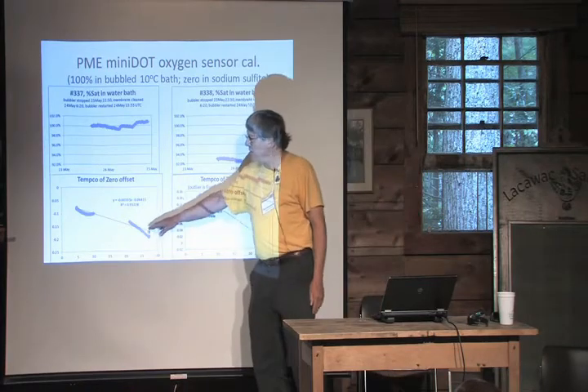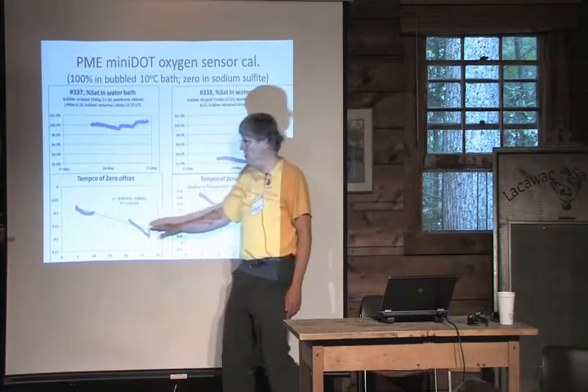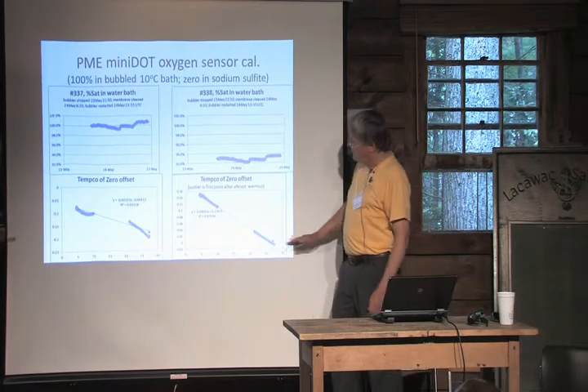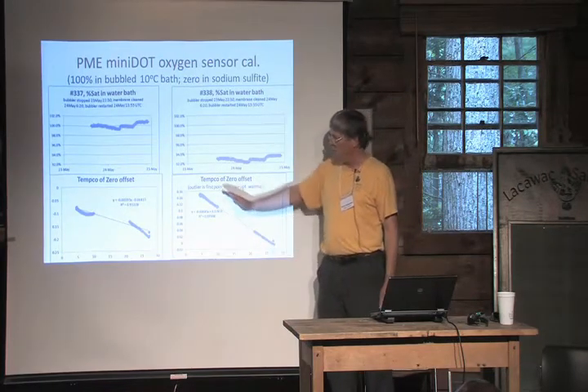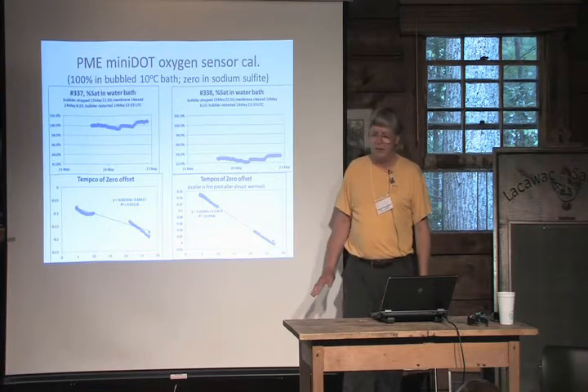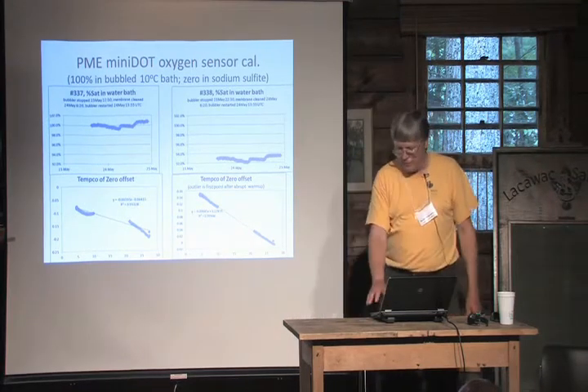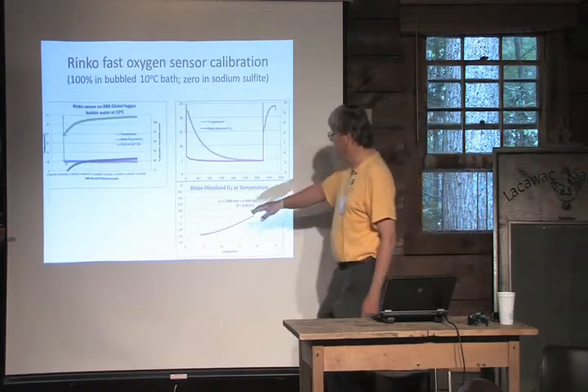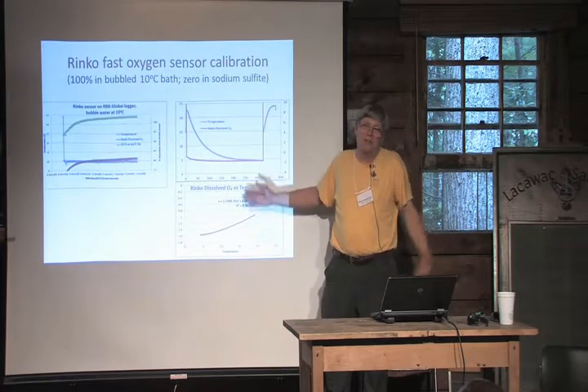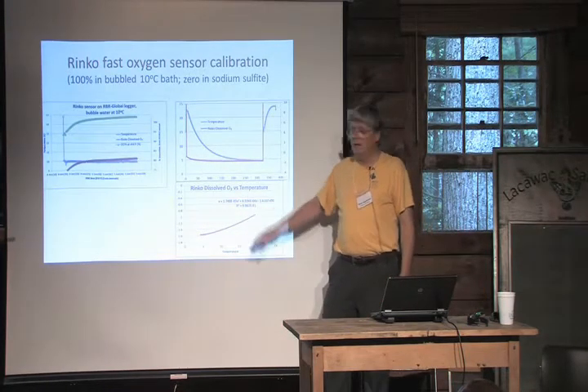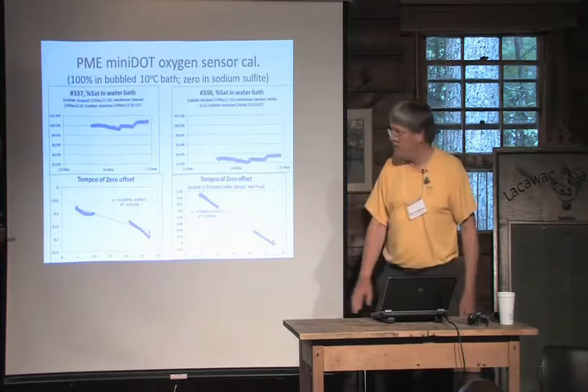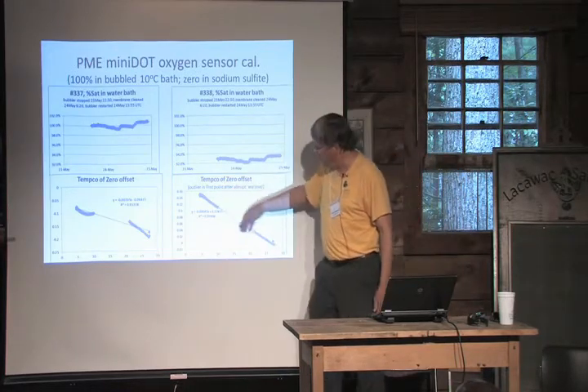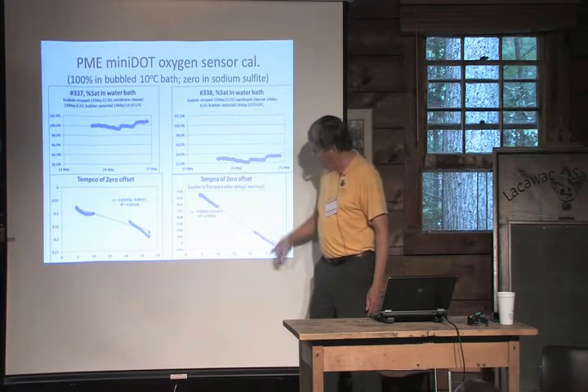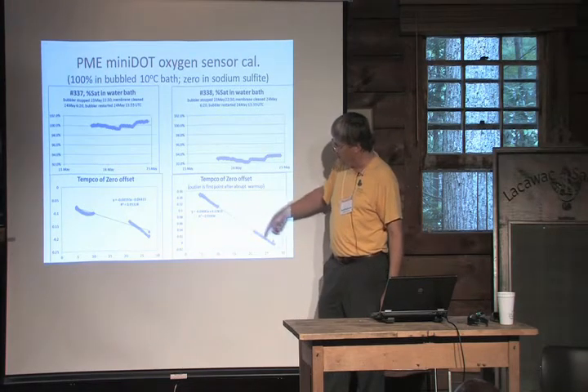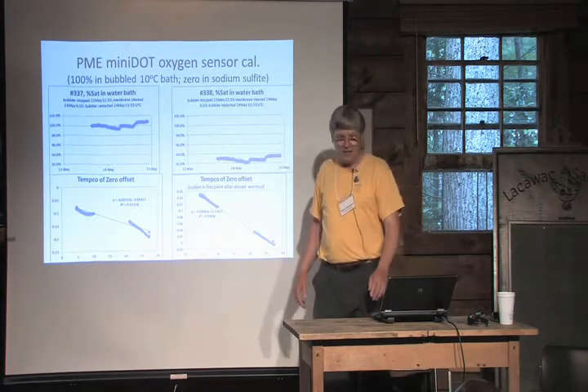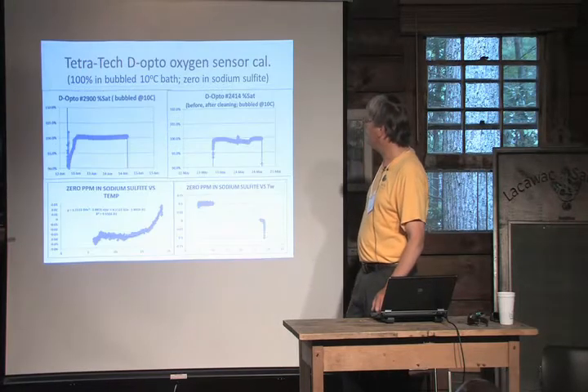Here again, put them in sodium sulfite, let the temperature change, and the 2 different sensors give a small change, but the same slope, negative. So a different response than the Rinko. And it's basically because the electronics are what are dictating this. And electronics are different. So it's easy to determine what the numbers are. In this case, I'm missing this middle ground because I started these at 10 degrees and went colder, and then did part of the warm temperature later instead of starting at room temperature. But it's an easy test to get the whole temperature range if you plan ahead.